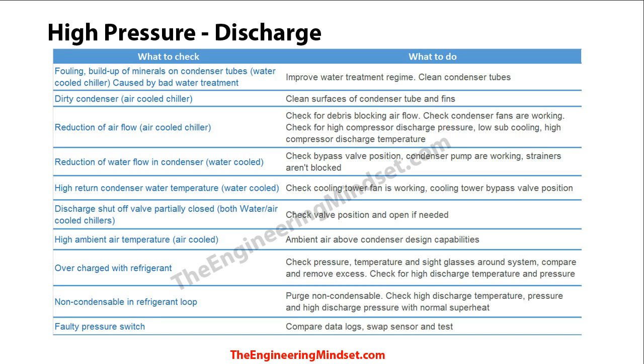You may also get a high pressure discharge fault due to reduced water flow through the condenser. Check all valves, strainers, and pumps to make sure they're operating at the correct flow rate. If you're unsure what the flow rate should be, refer to the commissioning data from when the chiller was installed — it will state the required flow rates through the pipework.